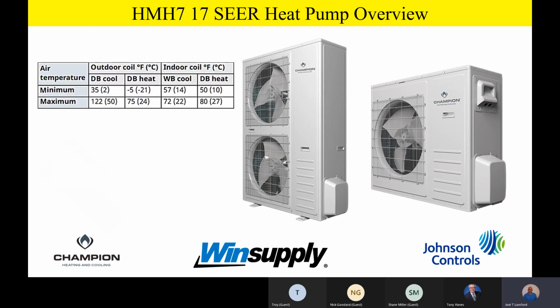A couple other good questions we get quite often when talking about the product, as a quick overview, are: at what temperatures will this work down to in the heating mode of operation, and what's the minimum cooling outdoor temperature? This little chart is right out of the install information. As you can see on the outdoor coil, in the cooling mode of operation, it'll go all the way down to 35 degrees.